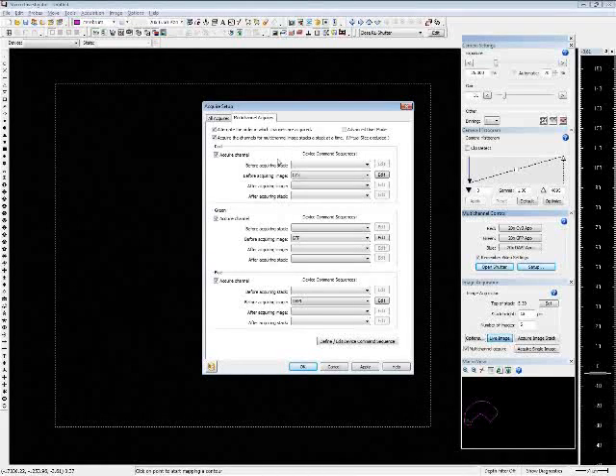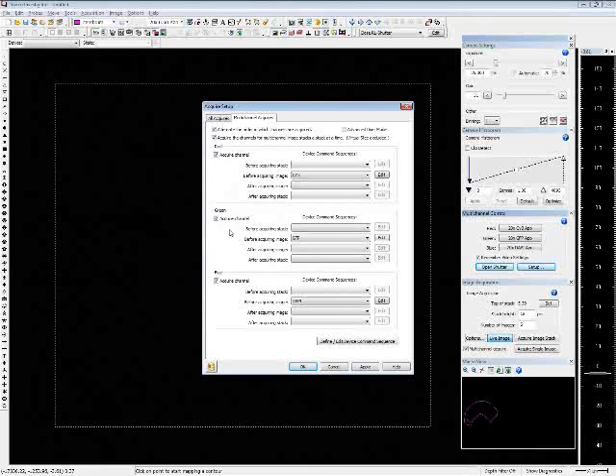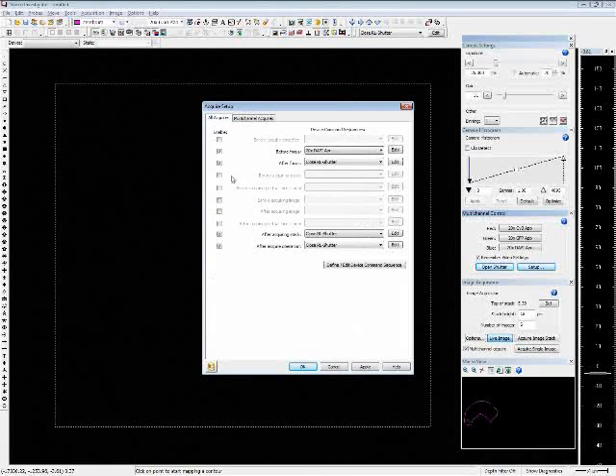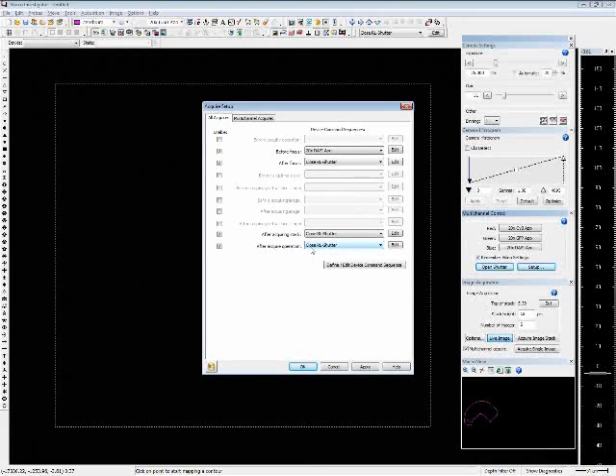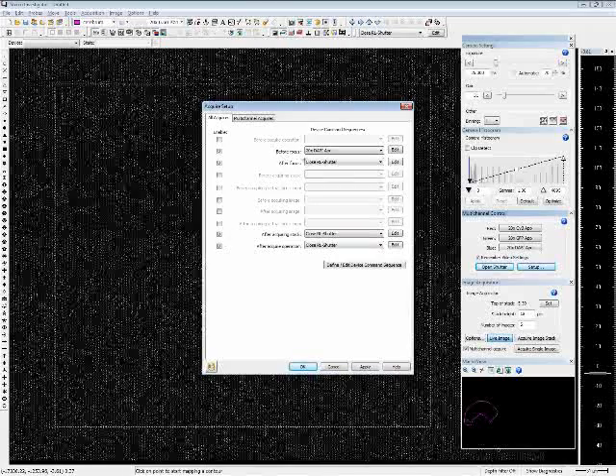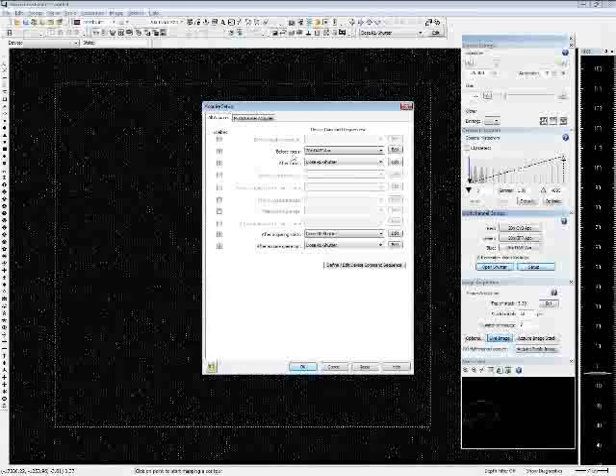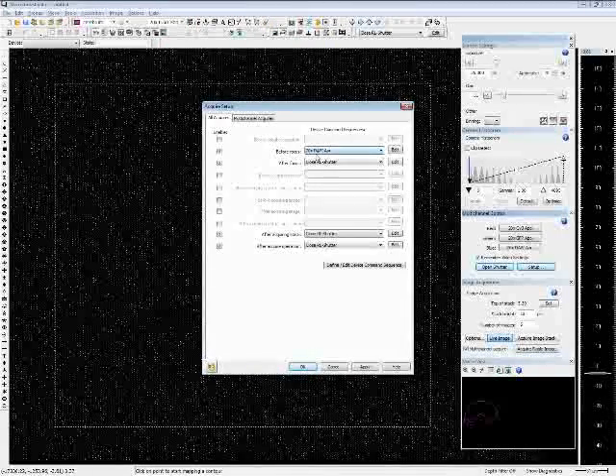When acquiring a stack at a time, all images for the red channel will be acquired first, then all of the green, then all of the blue. Under the All Acquires tab, I ensure that after every acquire operation the shutter is closed to prevent inadvertent bleaching. Additionally, after acquiring an image stack I'll request the shutter to close. Before focus — important for image stack acquires or virtual slice or virtual tissue — I request the DAPI channel be moved into position, and after that operation I ask for the shutter to close.